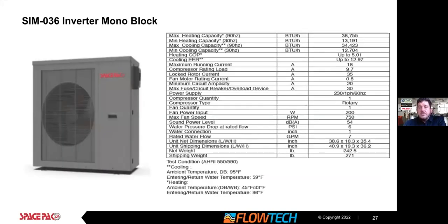Overview slide here. And like I mentioned, we're going to be sending all this slide deck out for all the detail, but the high points to touch on are the capacity based on temperatures that we talked about. Always understand your local conditions. One thing that's very important to note, and I will reiterate this throughout the presentation, is the pressure drop on the units is higher than a lot of technicians and contractors are accustomed to on piping equipment.